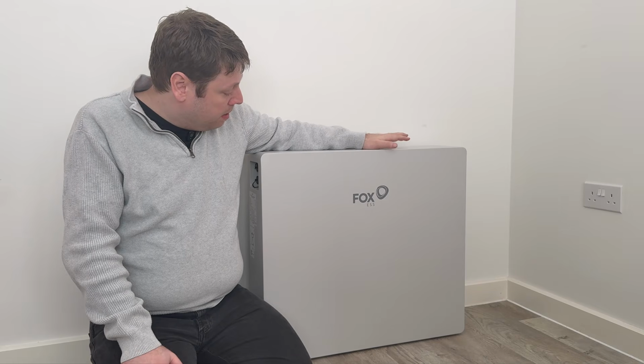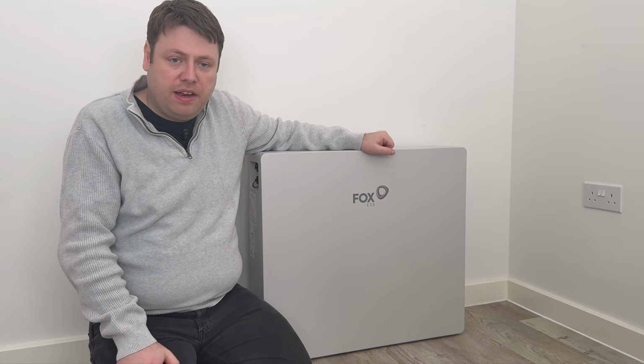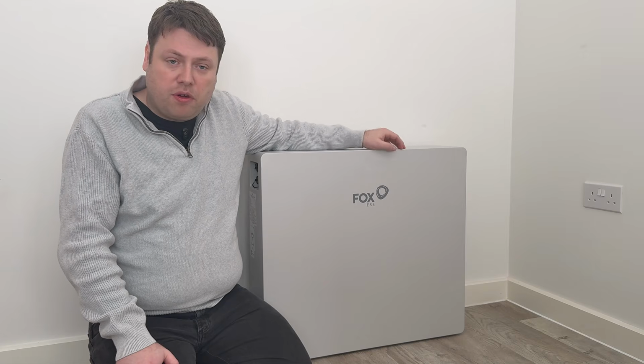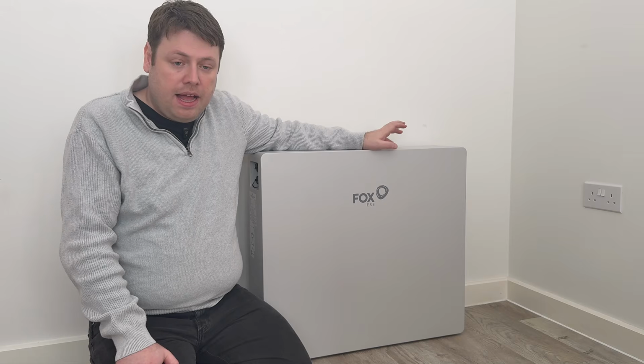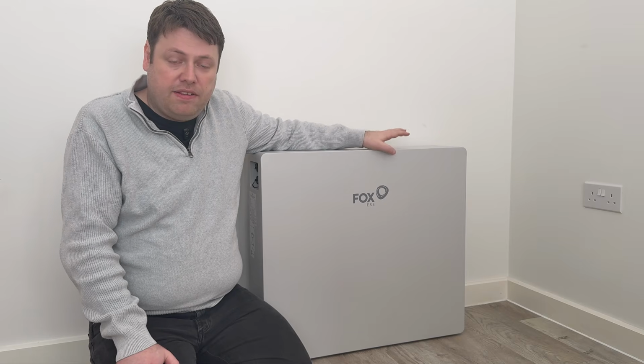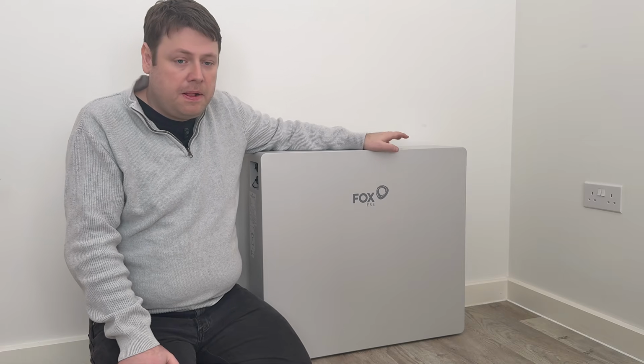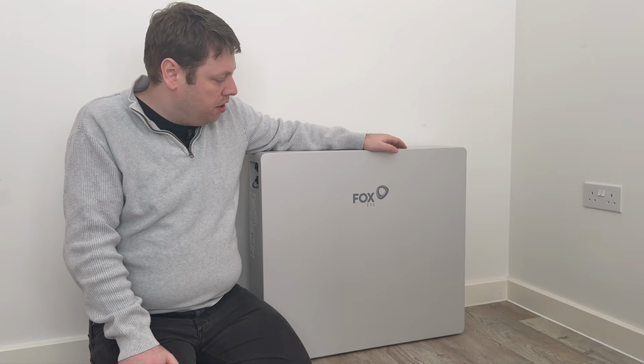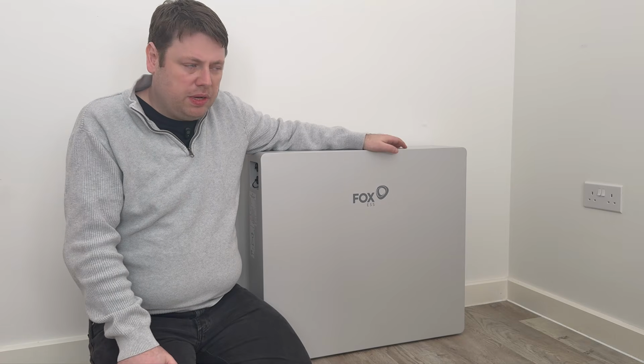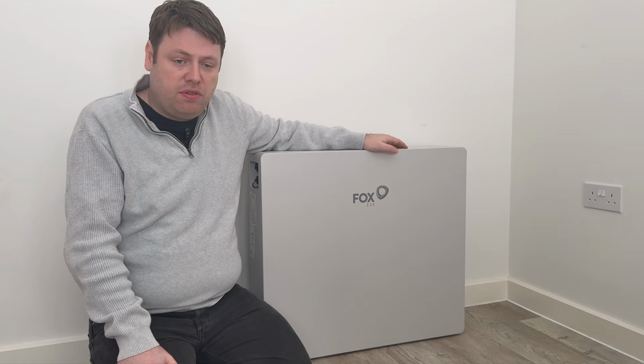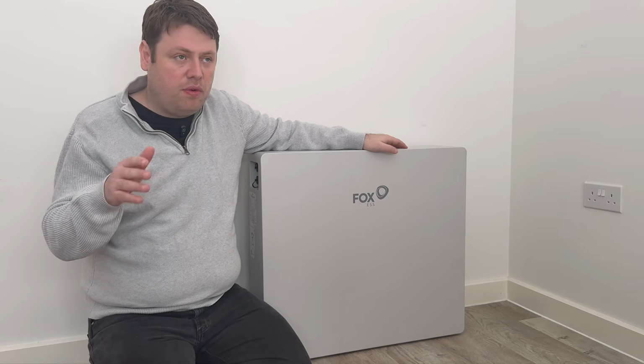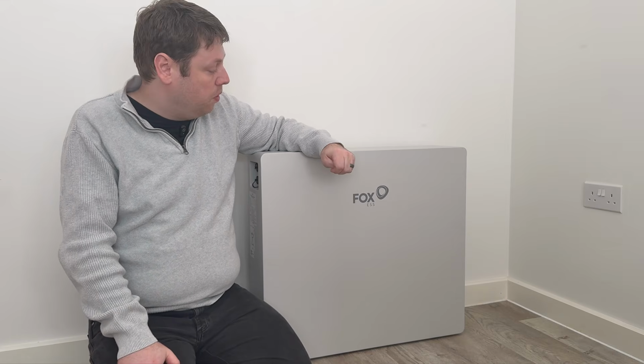So yeah, it's got all the bells and whistles, being the flagship model, with a heating or warming function to keep it warm and operating during those winter months, but also it's got fire suppression built into it. The performance of the battery: this is a high voltage system, so its nominal voltage is 384 volts. It goes right up to 438 volts when it's fully charged, or that's its maximum, and its lowest voltage will be down to 348 volts. So between 348 and 438 is its voltage range, with nominal described as 384.